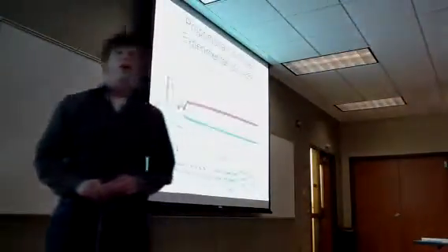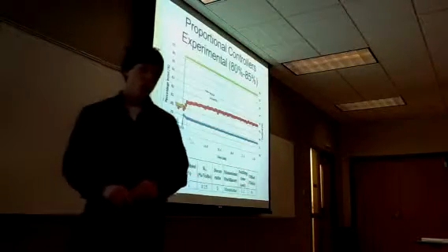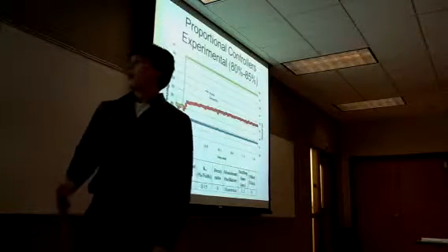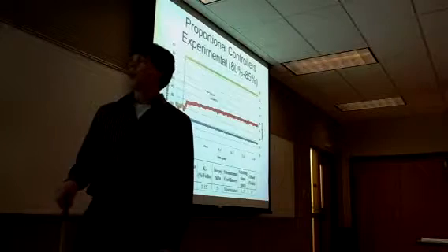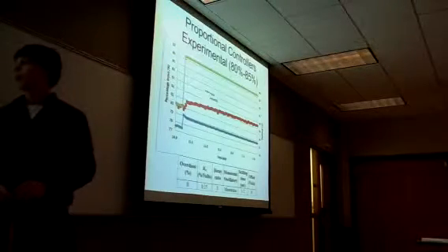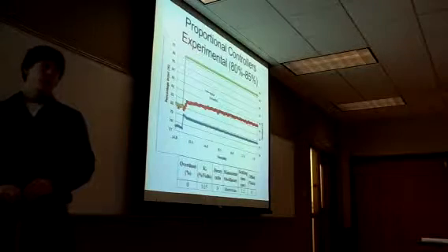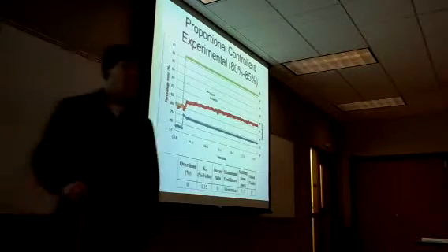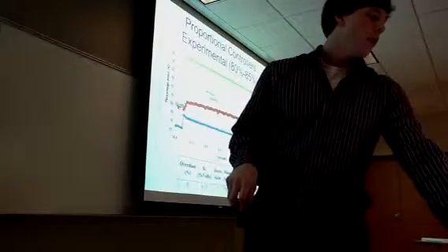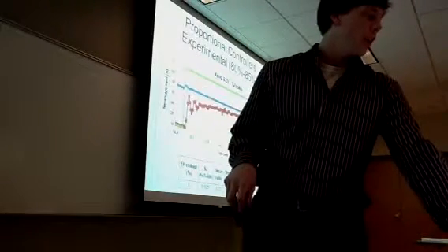These are examples of the experiment part of the proportional only controllers. This is for the 80 to 85% input region, and this is how we found the critical damping. We found it to be 0.15% per volt for KC.